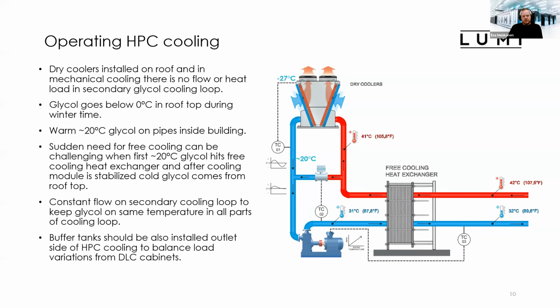And if there is a sudden need to turn from mechanical cooling to full free cooling, so that we are stopping the heat production, this will cause problems, because first the 20 Celsius degree glycol is coming to the heat exchanger, and we have this mixing valve here, so we are trying to keep this 31 degrees for the heat exchangers. A sudden heat load hits the free cooling heat exchanger, and this pump needs to start ramping up to maintain the 32 degrees on this side. And then we have sudden incoming -27 degrees Celsius glycol from the rooftop, and we are still mixing some flow into it, and suddenly this drops dramatically. So we need to start mixing more heat into the incoming glycol from the rooftop, and we need to start to lower this pump speed because this outlet goes too low.